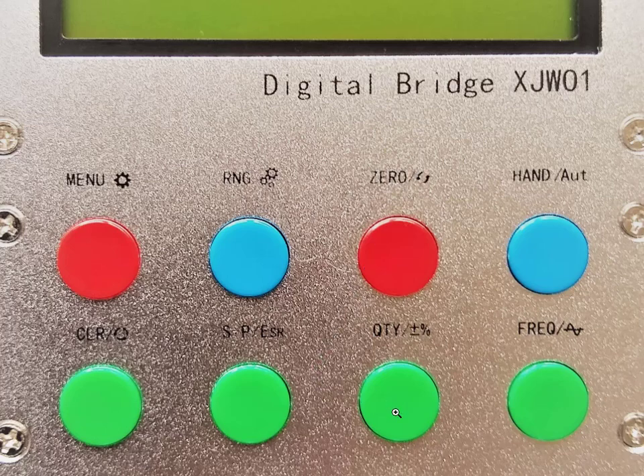The next button is marked quantity, and this again really should be marked as relative percentage. So you put an exemplar standard component connected to the meter that you want to compare with other similar components, and you press this button. That will record the value that's currently being measured as the exemplar or standard value. You can then disconnect the component and connect similar components of the same or similar value, and it'll show you the percentage difference and also the actual reading of that component.